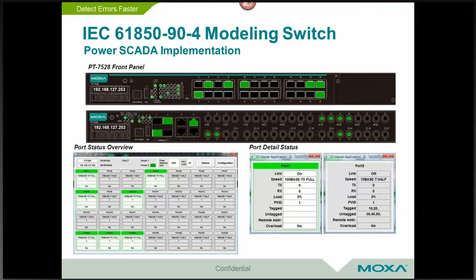Another feature for detecting errors faster is a fiber check mechanism. Most people don't realize fiber transceivers can wear out over time - when that happens, you need to know when they're about to go out. By over time I mean something like 8 to 10 years. That's a long time, but the bottom line is you'll be using a lot of this communication gear for the next 10 to 20 years. So it's a good idea to know if things are starting to wear out, and get a notification sent via the MMS protocol back to your SCADA system saying: hey, your IEDs are working okay, but I want to let you know your communication infrastructure is at risk right now.